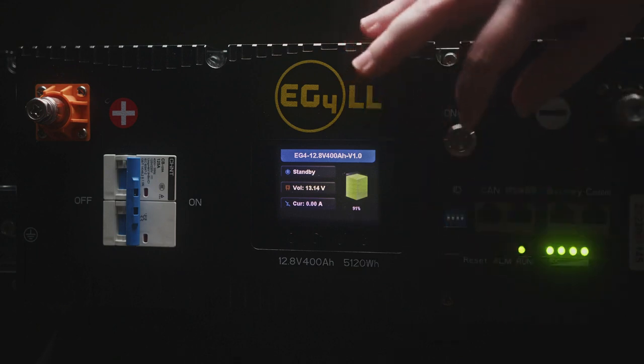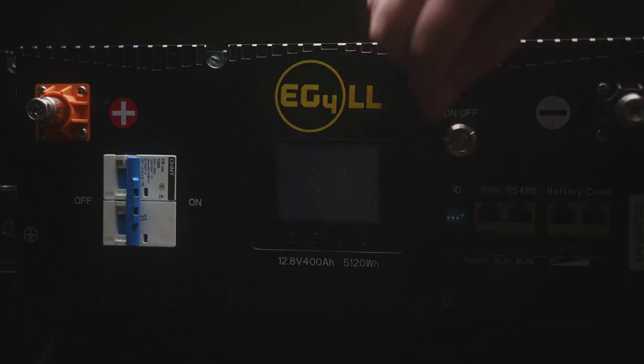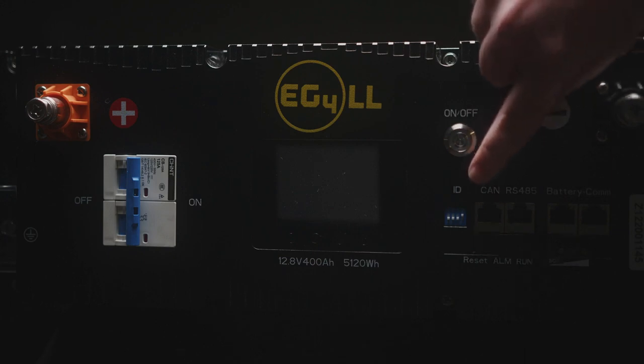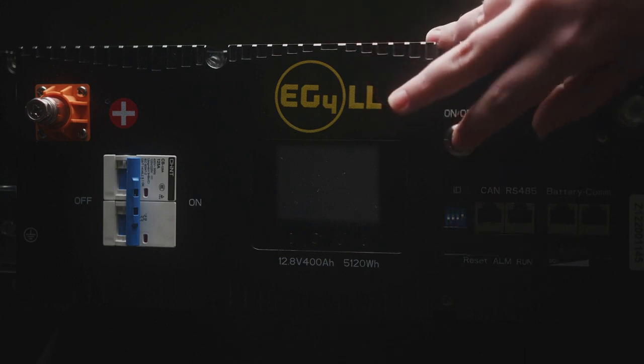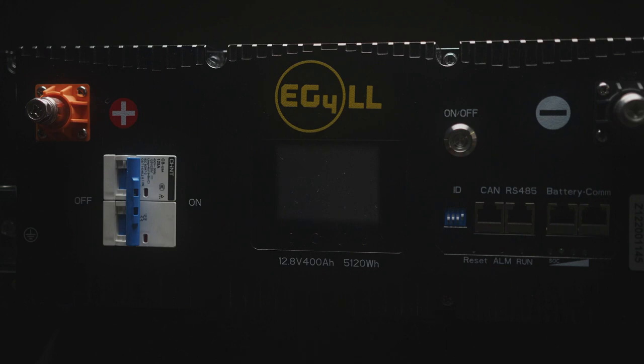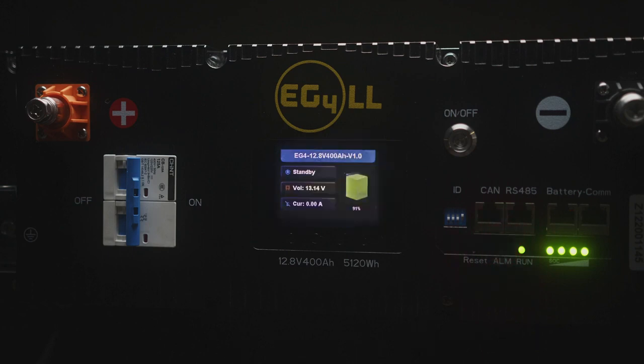Then you want to make sure your battery's off, that you have the dip switches set to down, down, down, up. You want to power your battery back on, and that will set it as the master battery for the Victron protocol communication. And with the proper CAN cable, you will be communicating your V2 battery to the Victron system.